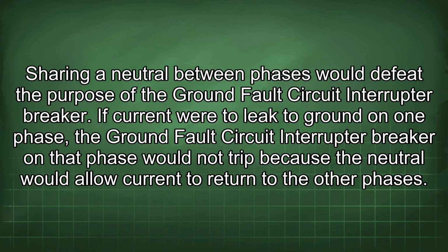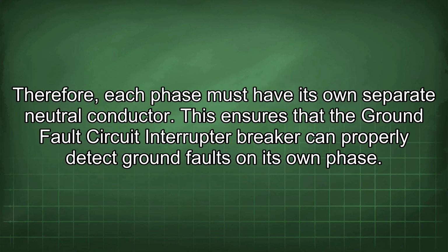If current were to leak to ground on one phase, the ground fault circuit interrupter breaker on that phase would not trip because the neutral would allow current to return to the other phases. Therefore, each phase must have its own separate neutral conductor. This ensures that the ground fault circuit interrupter breaker can properly detect ground faults on its own phase.